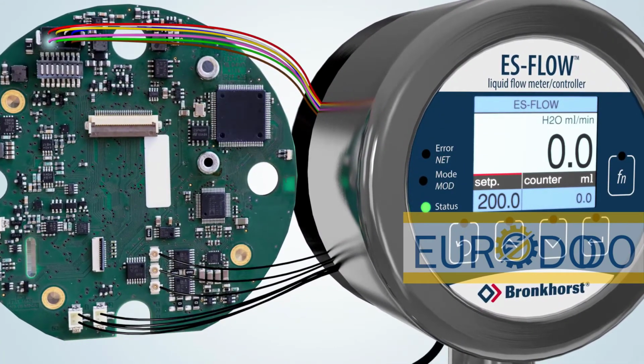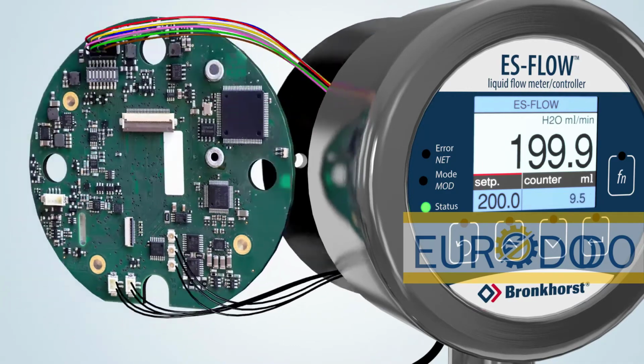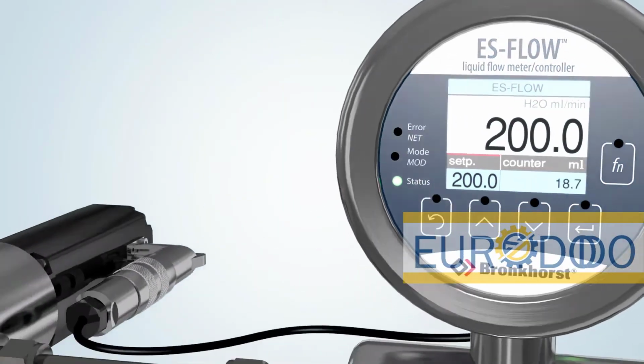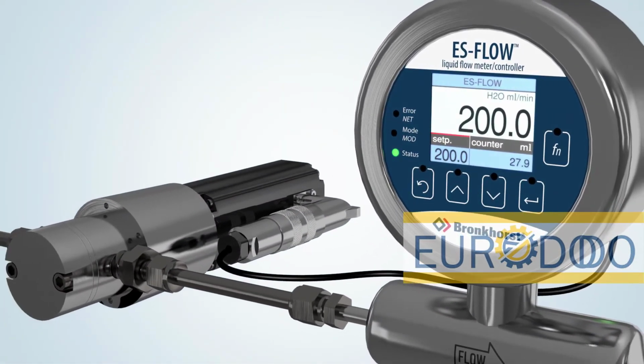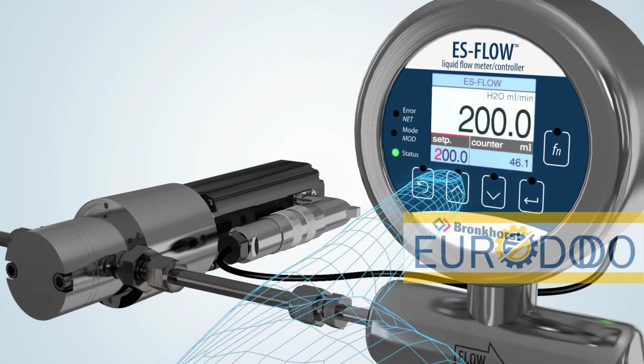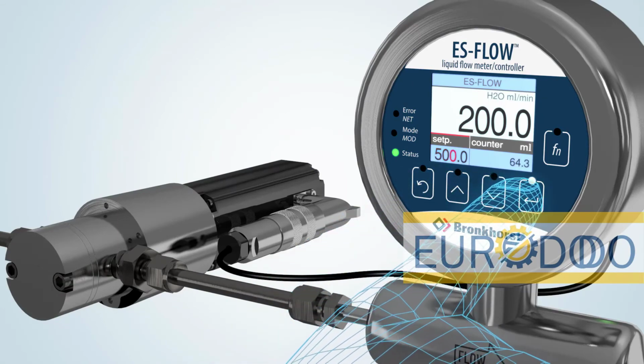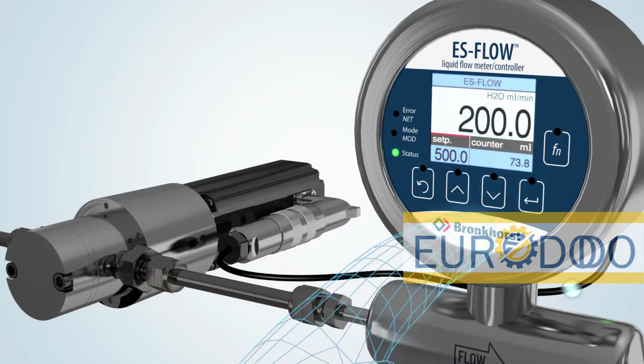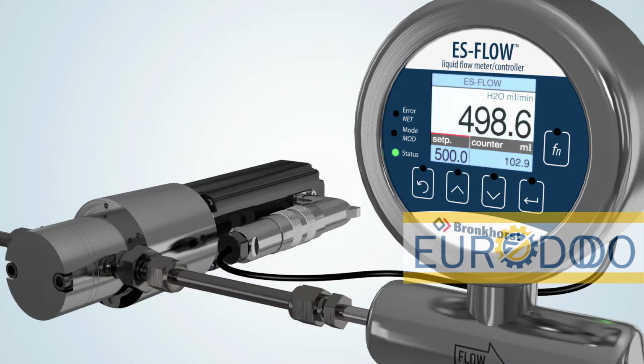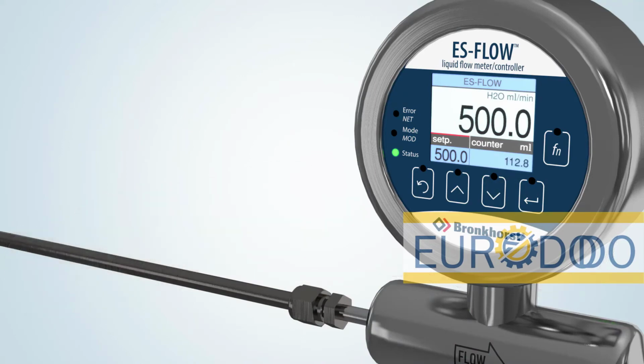This measuring principle is highly accurate, very fast, insensitive to vibrations, and, as mentioned before, independent of liquid properties such as density or viscosity. For liquid flow control, Bronkhorst combines the ES-FLOW with a close-coupled pump at the inlet of the flow meter. Upon set point change, the integrated PID controller adjusts the speed of the pump in order to set the flow to the required value.